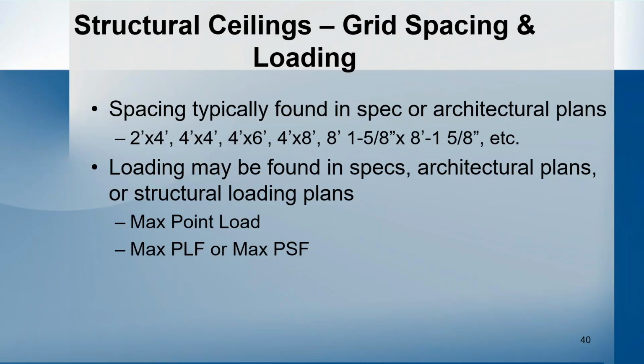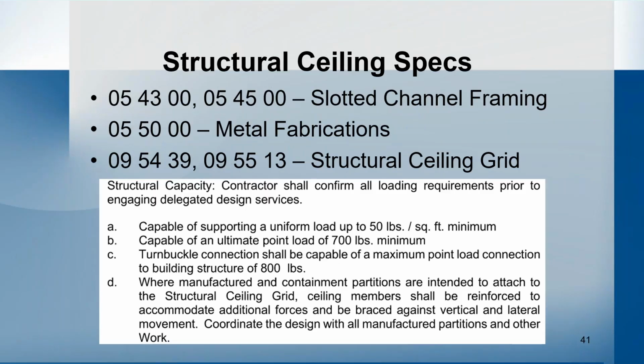So when you're loading for these, they're found in a number of different places. It could be the specs, the architectural plans, or structural loading plans. And they're often listed as a max point load, max PLF, or max PSF. Sometimes you need to account for multiple of those as well. And as far as the specs, where they can be found, we've seen them in a number of different places: slotted channel framing spec, metal fabrications spec, the structural ceiling grid spec. So it can be found in pretty much any of these possible locations.